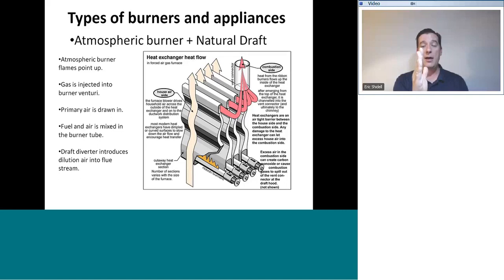Just try and make that flame go sideways. You can turn your whole lighter sideways, and that flame will still point up. A candle is also an atmospheric burner, and these gas burners are atmospheric burners as well. Flames will point straight up and down. The combustion products will be drawn upwards through the heat exchanger, and they will leave the heat exchanger in an open area. Because the flue is under a draft and it is pulling up, it will pull those combustion products up right with it, and it will also pull dilution air in from the other end up with the flue products.